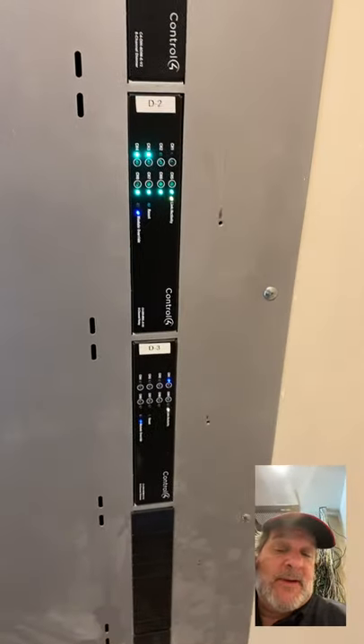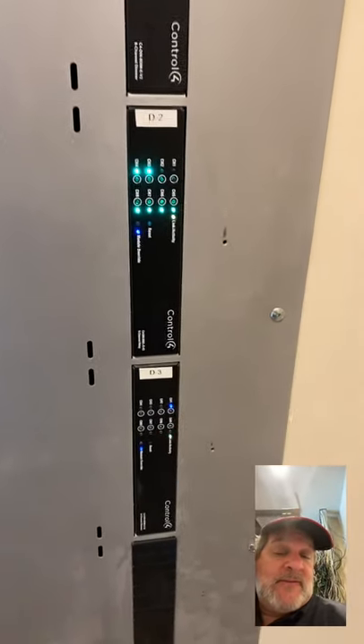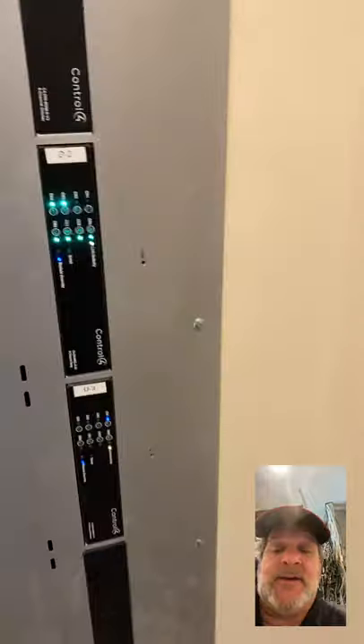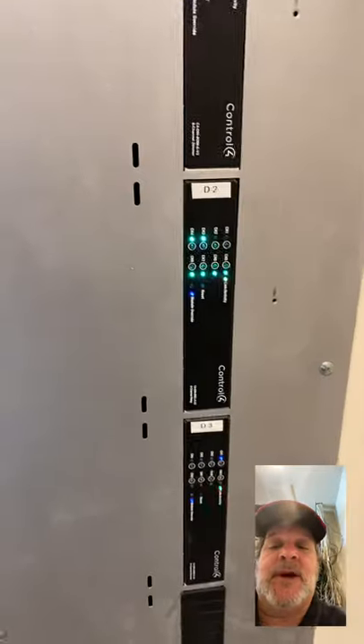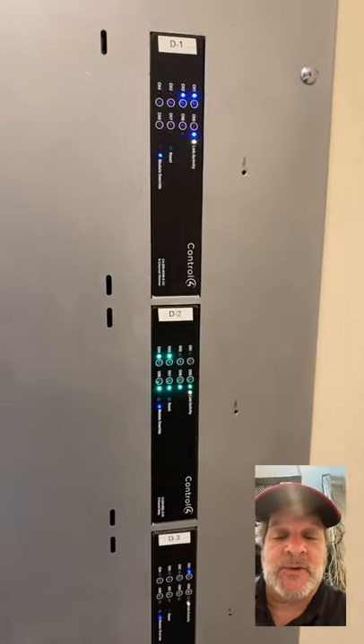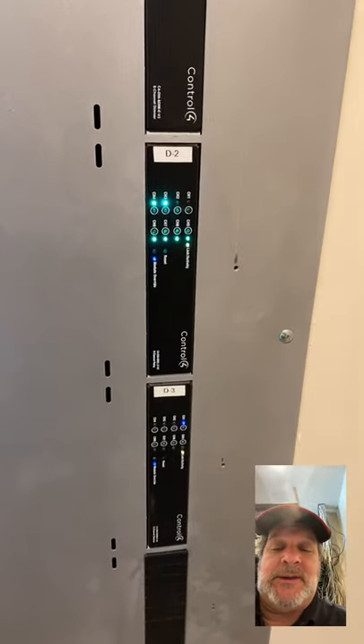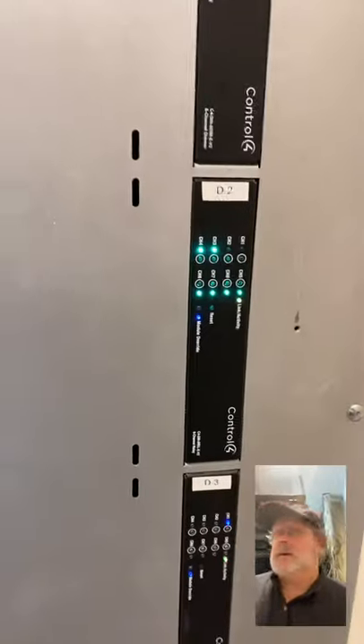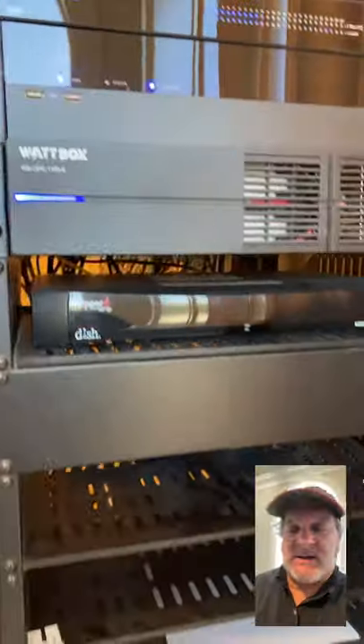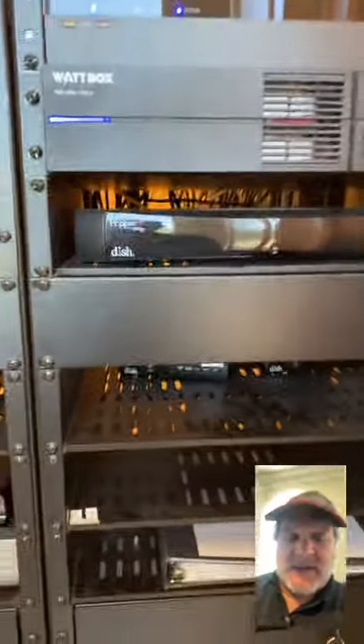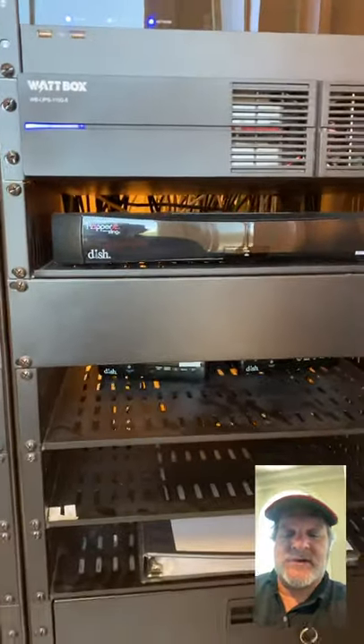So I've got 10, 15, 18 of these modules in total controlling lighting, and all that's controlled by Control4. We added a Control4 switch here for the exhaust fan and there's a thermostat built into the rack, so when the temperature exceeds 88 degrees it automatically kicks in the exhaust fan.